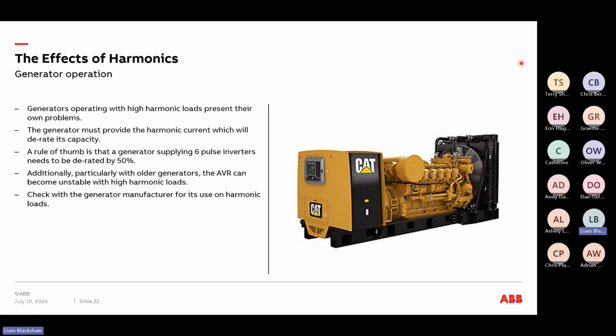Again, being biased, when we look at variable speed drives, we normally say, as a rule of thumb, you tend to derate that by about 50%. So if you're using a traditional 6-pulse drive, let's say 100 kilowatts, for example, you would rate your generator to be 200 kilowatts, and maybe slightly more if it was a transformer. So instead of eliminating harmonics, it's kind of managing them, overcompensating for them.